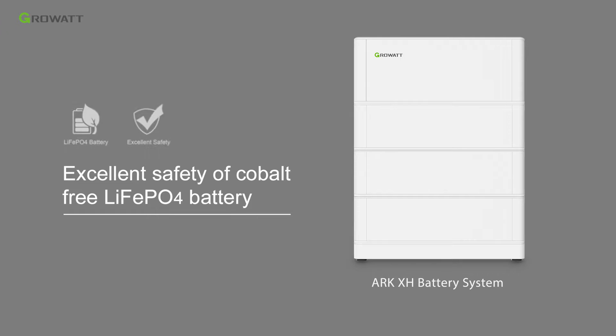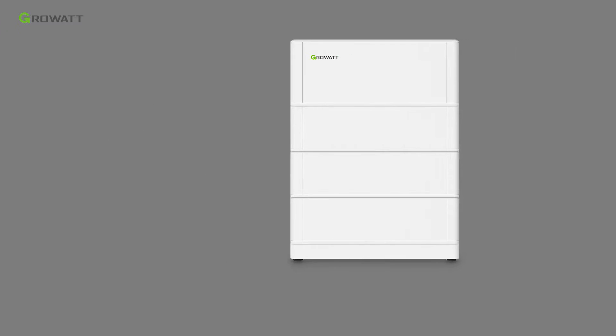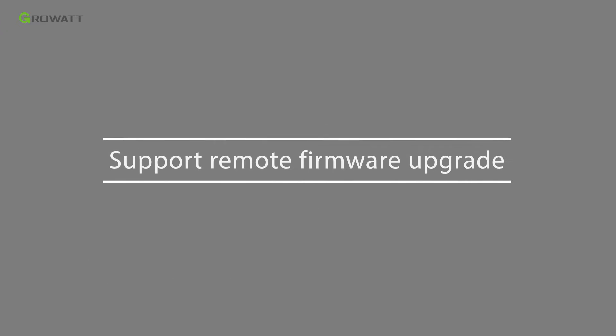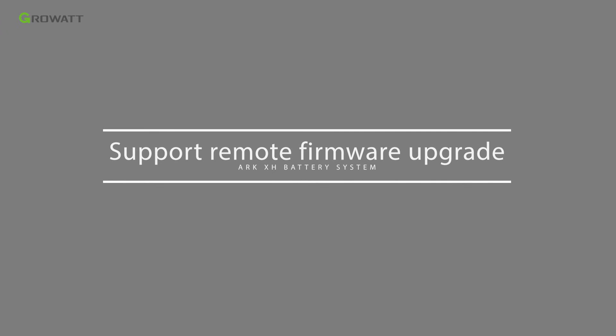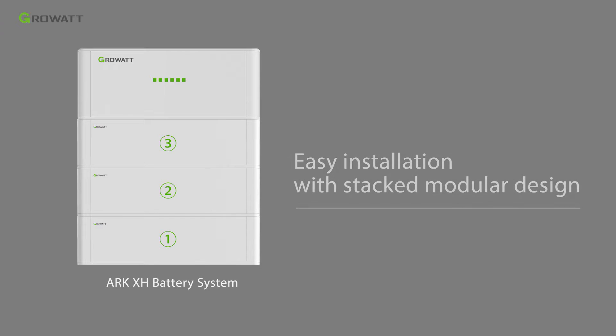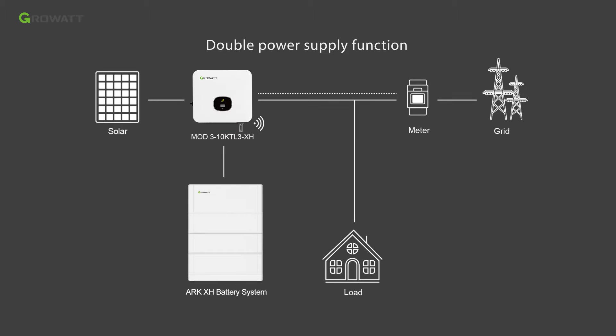ARK battery uses cobalt-free lithium iron phosphate material to guarantee excellent safety. Offering flexible capacity options for customers, each battery module is 2.56 kWh, supporting from 3 to 10 pieces in series, and supports remote firmware upgrade to save on-site maintenance costs. The whole system features easy installation with a stacked modular design and supports double power supply function. A MOD10KTL3XH inverter can provide 10 kW full power AC output plus 10 kW full power battery charge capacity.